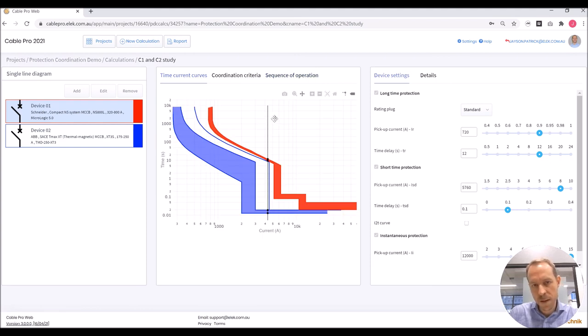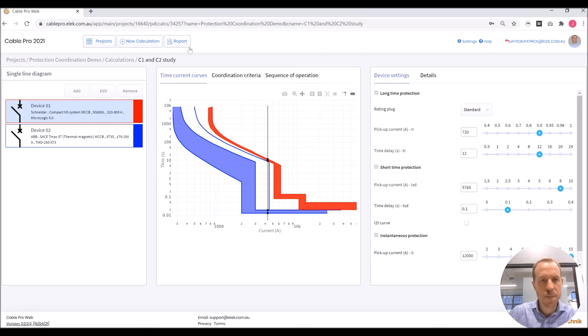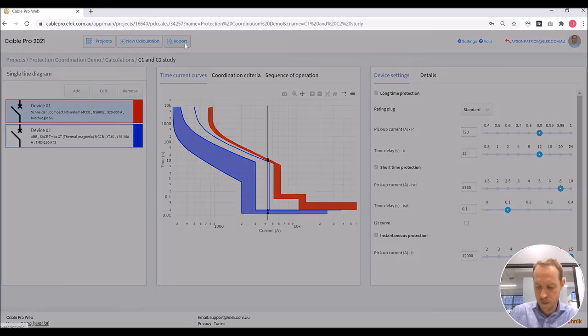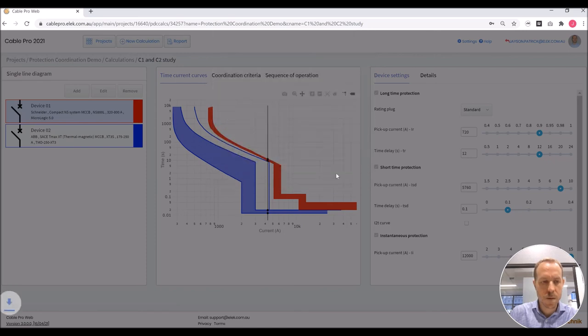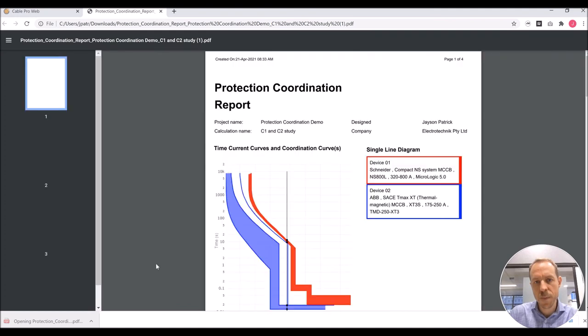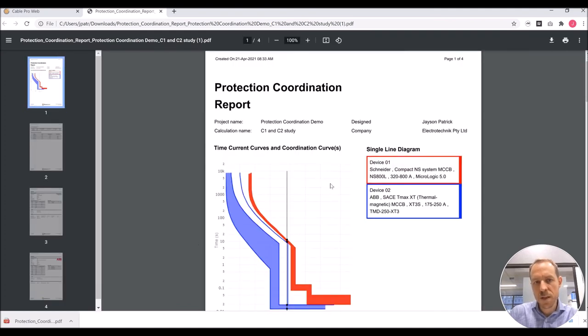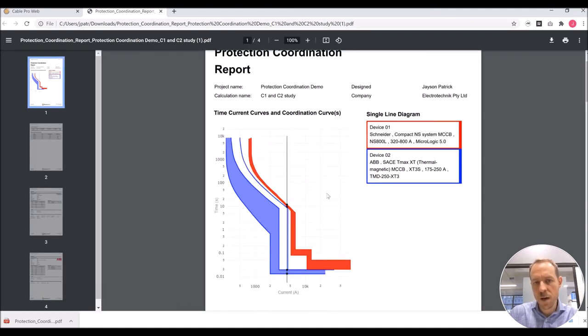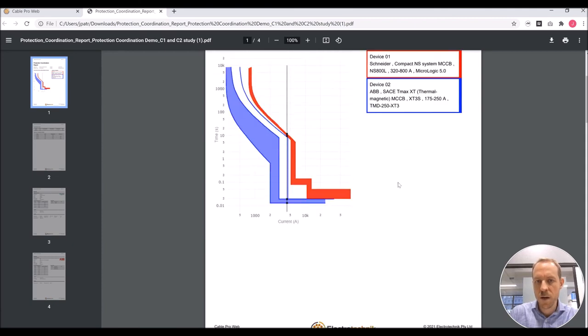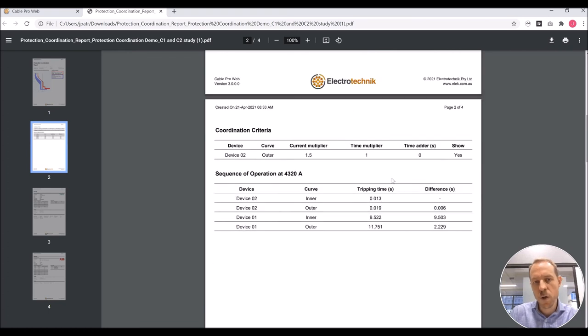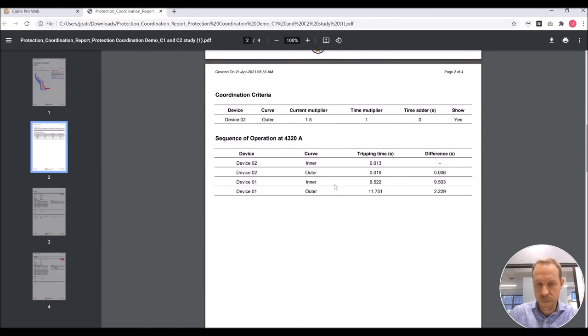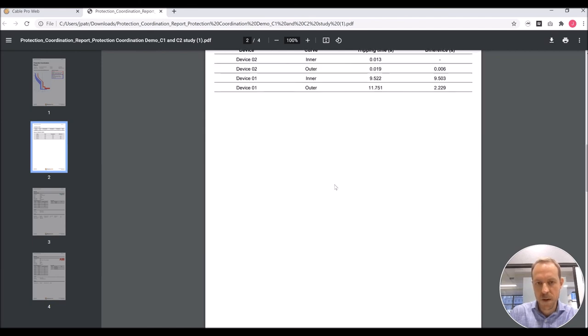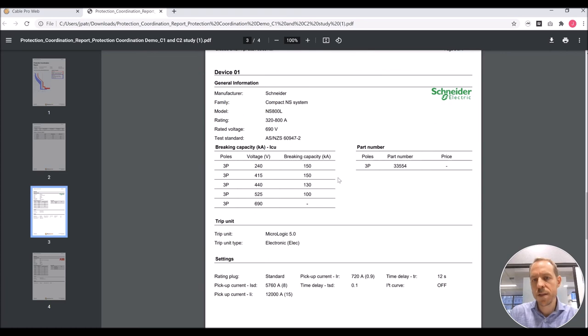And that curve is shown here as a vertical line. Finally, we can print a detailed report. I will just open this PDF. The PDF contains the time current curves and the single line diagram. You've got the coordination criteria and the sequence of operation.